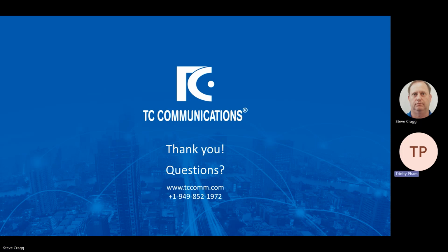This next question came up when you were talking about the TC8631. What baud rates for serial can TC Communications support? Right. The general baud rate is 38.4 kilobits per second. Under certain circumstances, that can be increased to 64 kilobits per second. But to be safe, in all cases, 38.4 kilobits per second.